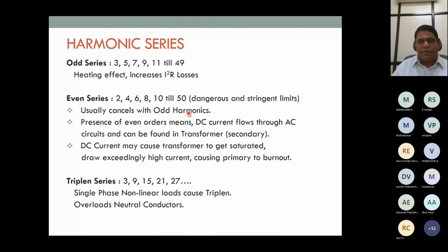So harmonics are categorized as orders: first order, second order, till 50th order. In those orders, whole numbers, there are three series. One is called odd series, second is called even series, and third is called triplen series. The general effect of harmonics is heating, heating of conductors, heating of transformers, and all. The special characteristic of the odd series is that, in addition to the heating effect, it increases our I squared R losses, which is called the power losses. The even series usually cancels with the odd series, and in excess, it will be creating a lot of difficulties to the transformer we are using.